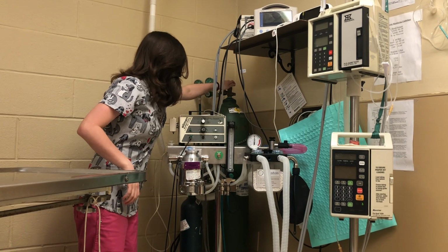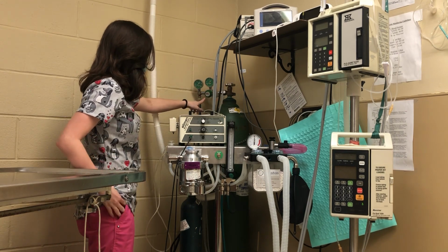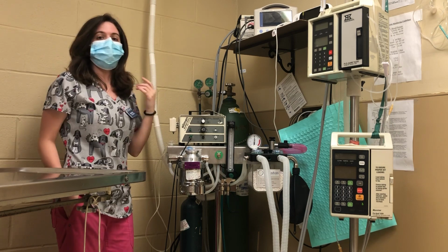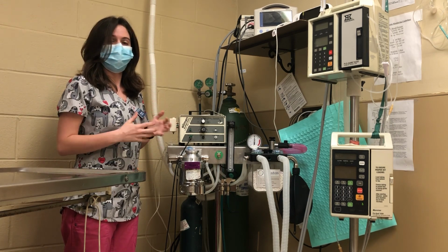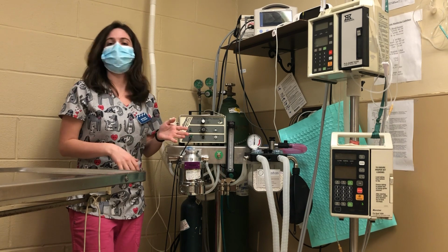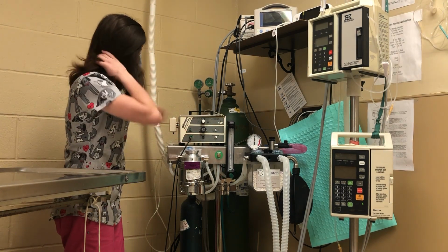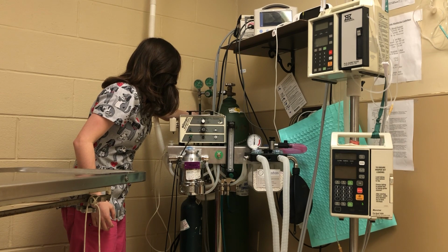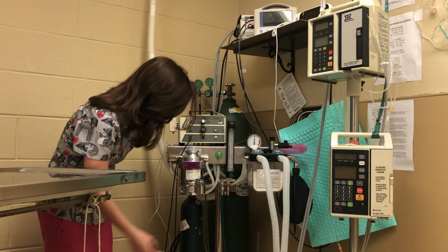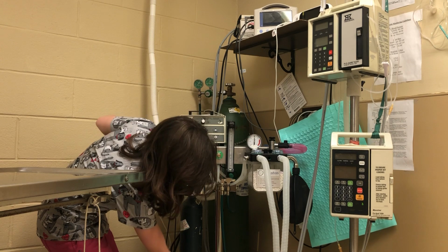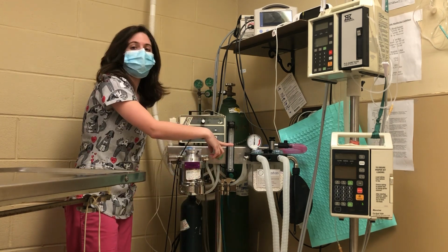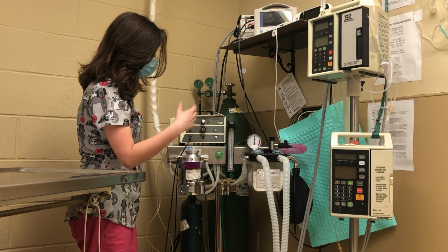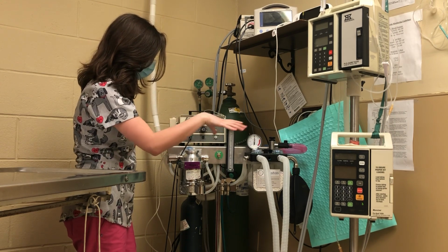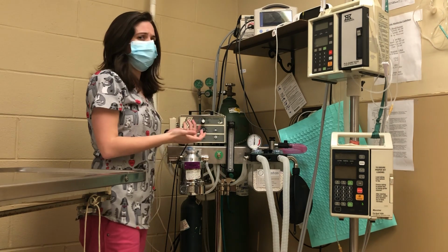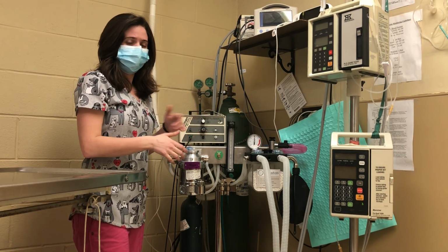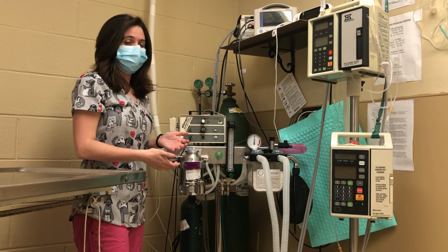So what we would do is we would turn this on. It goes into our pressure regulator, which will reduce the pressure of the gas to a more usable, safe level, which is about 40 to 50 psi. And then it's going to go down into this intermediate tube down here, and I don't know if it might be a little hard to see, but it wraps around here and goes into our flow meter. Our flow meter kind of tells us the rate of how much oxygen is going to be in the rebreathing system at a time, and it can also further lower the pressure of the gas.